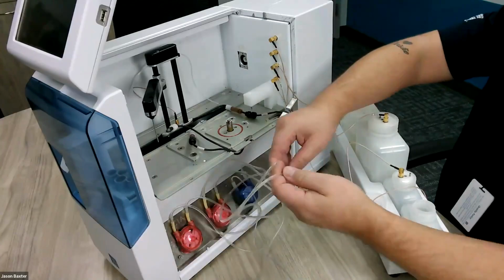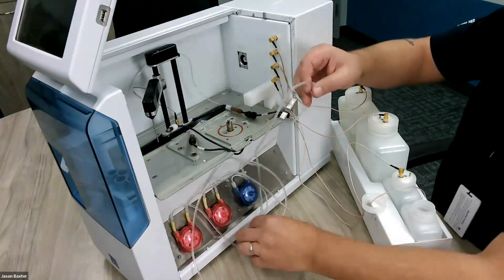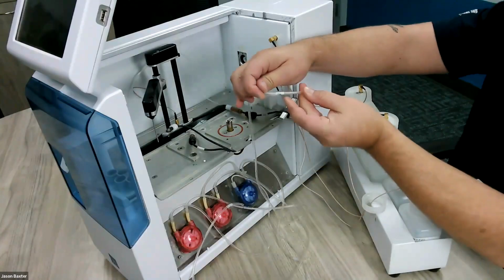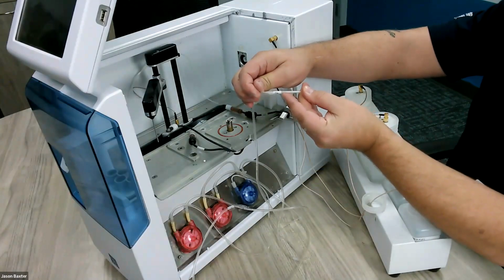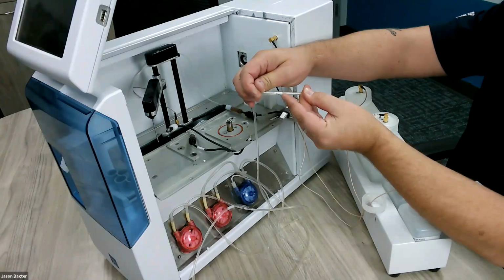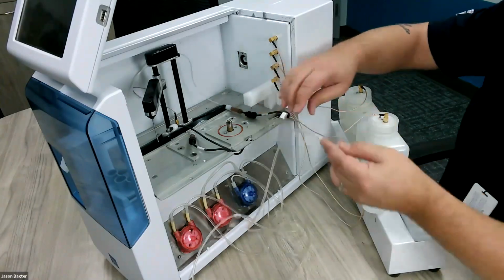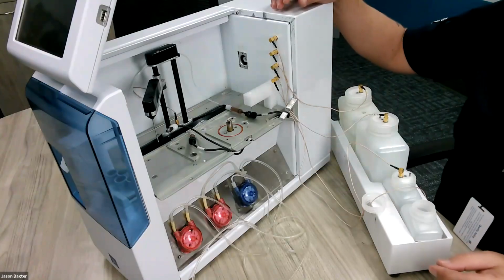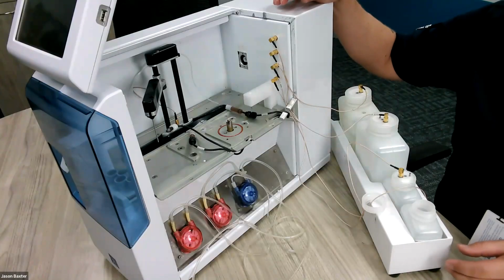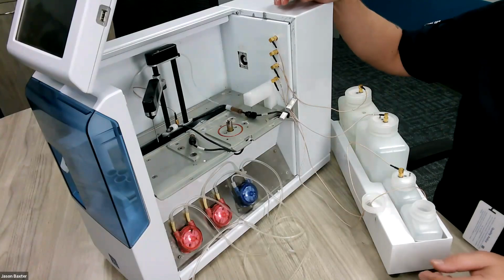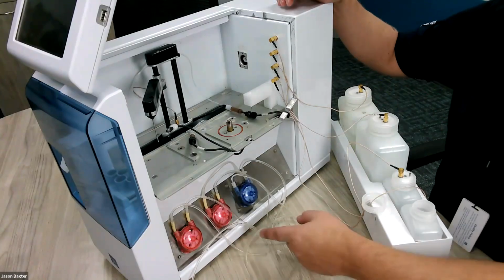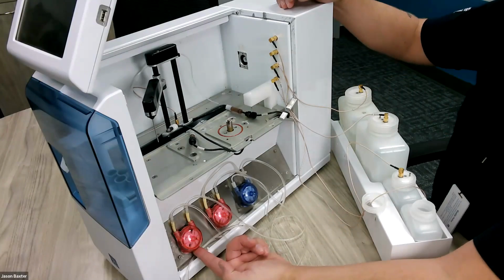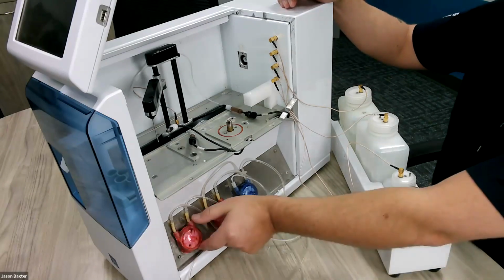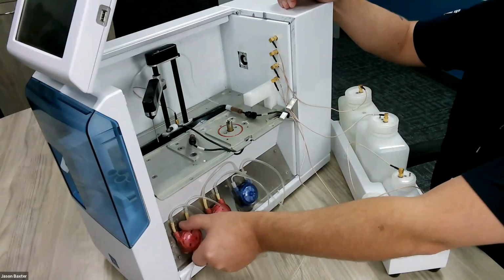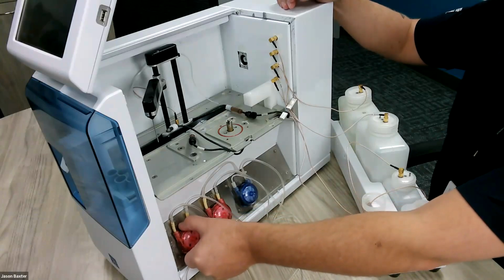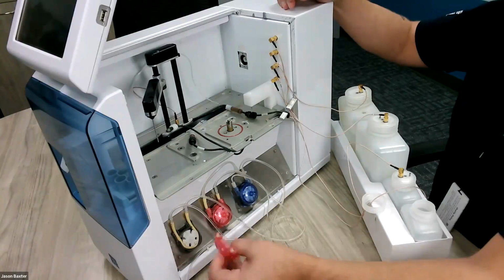One thing of note that we'll see again at reassembly is that each one of these lines has a label on it that will identify what terminal it should attach to. So we made that a lot easier. All the tubing in the PM kit is pre-cut, so there's no guesswork, there's no magic. It's very straightforward. To remove these peristaltic pumps, I like to put my index finger down at the bottom of the cap, and then I hook my thumb in on the top, just of the red portion, and I can pull it out, and you should hear a faint click as it lets go.